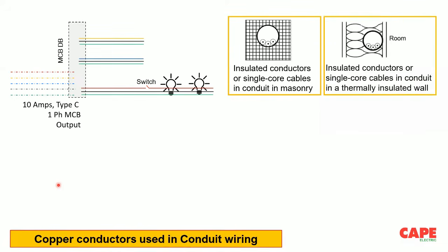Number 2, copper conductors used in conduit wiring. You know very well about conduit wiring. I have spoken about this subject on several occasions, not for the first time. Copper in the wire generates heat. Once we pull the copper wire through an enclosed space, such as a conduit or trunking, the amount of heat generated inside this confined space must be limited, for example, to not more than 70 degrees. If the temperature goes above 70 degrees, you end up with trouble.